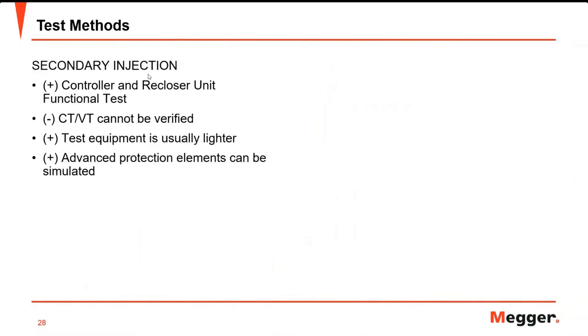The other way is through secondary injection. Both the controller and the recloser unit functional test can be performed at the same time. For more detailed testing, the recloser unit can be isolated so as not to subject it to more open and close operations. The built-in CT and VT cannot be verified. Test equipment is lighter compared to primary injection. All protection functions can be simulated, including GPS-aided tests in a smart or self-healing grid.